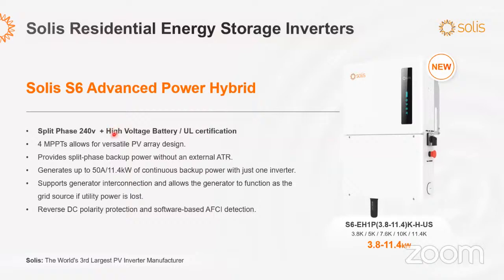The inverter can only be used with high voltage lithium batteries. We do have a compatibility list with the major brands, being Pylontech, Soluna, LG, BYD, Fortress, and more to come. It has a UL certification that includes also rapid shutdown models and transmitters. And one of the key characteristics of this inverter is that it has one-to-one backup power without any autotransformer. Autotransformers are used a lot in the Caribbean because they have European hybrid inverters with different voltages, different configurations. So they have to use an autotransformer. This inverter is completely plug and play. If you want to look more about this, we have plenty of information in English and Spanish. Because this inverter is mainly designed for the US, Mexico, and of course, all the Caribbean.